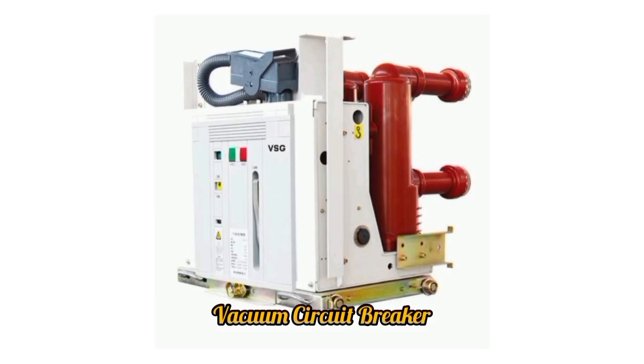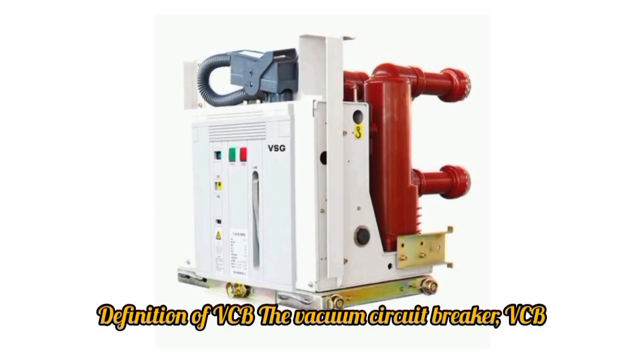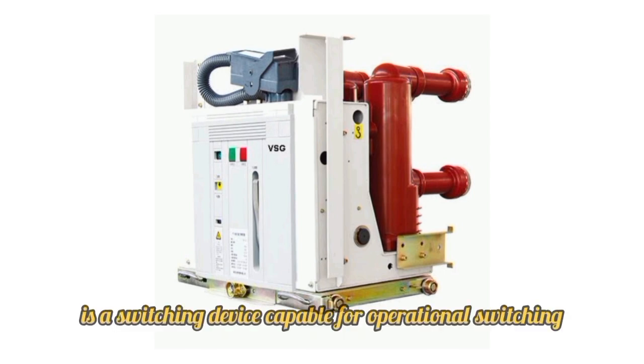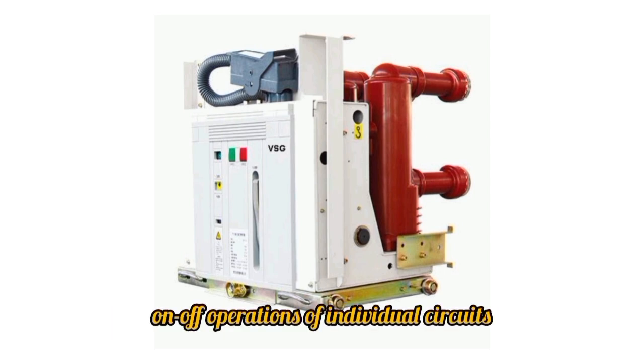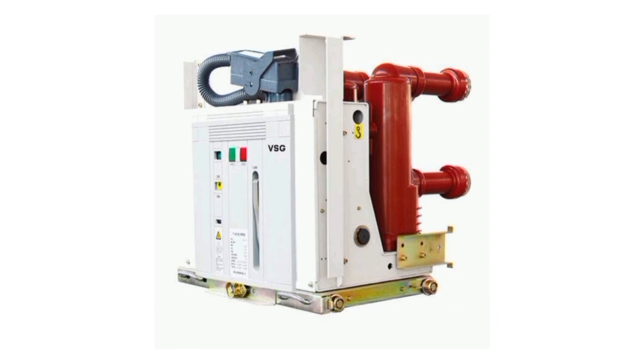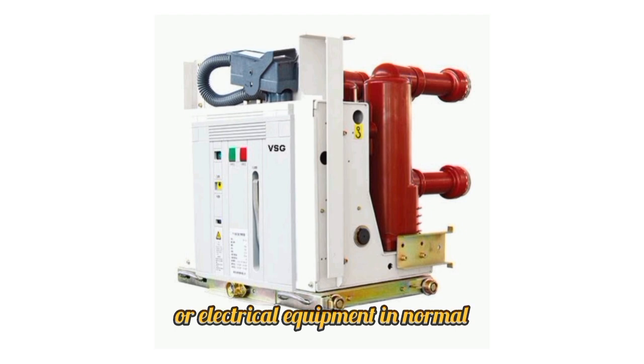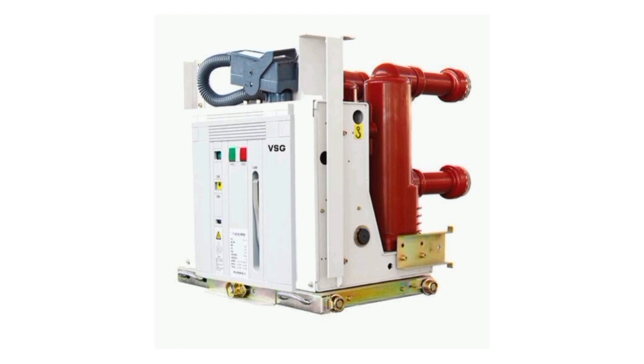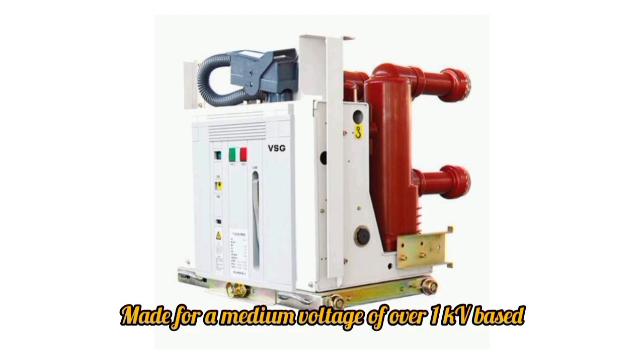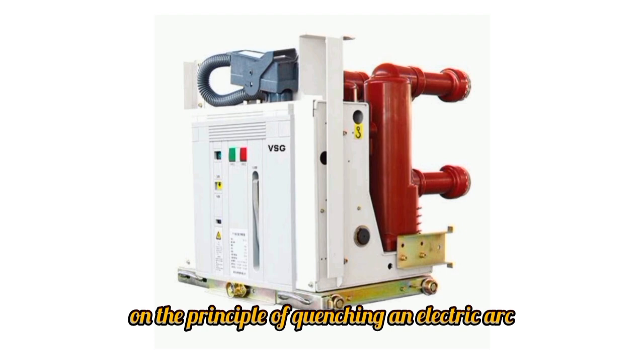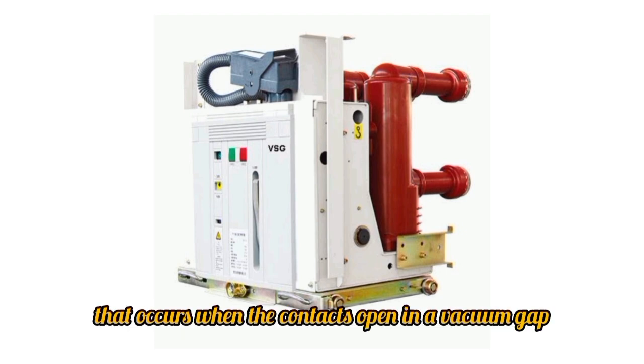Vacuum circuit breaker. Definition of VCB. The vacuum circuit breaker, VCB, is a switching device capable of operational switching, on-off operations, of individual circuits or electrical equipment in normal or emergency modes with manual or automatic control. Made for a medium voltage of over 1 kV, based on the principle of quenching an electric arc that occurs when the contacts open in a vacuum gap.